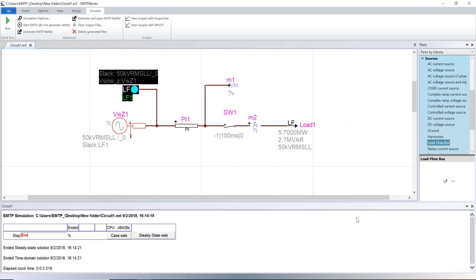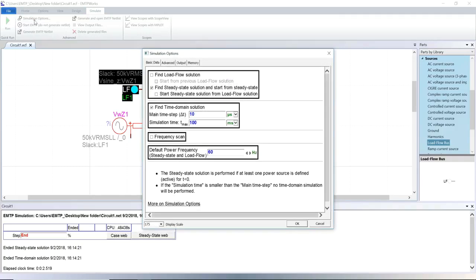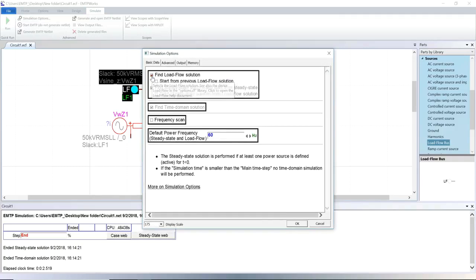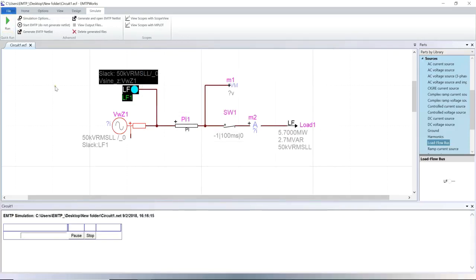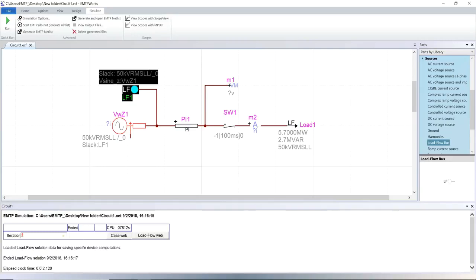Our circuit is now ready for the load flow calculation. To run it, go to simulation options in the simulate tab and check find load flow solution. Click on the start button. The load flow conditions have been found. The load flow solver uses an iterative Newton method for solving its systems of equations. The number of iterations required is noted in the console.